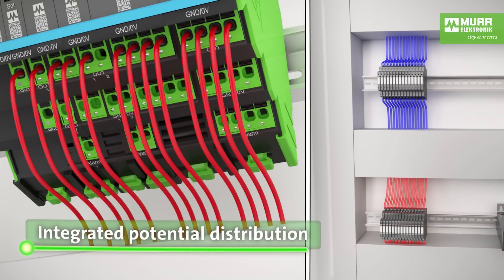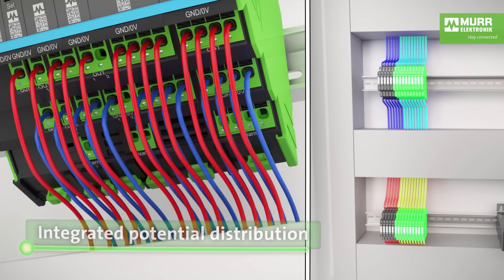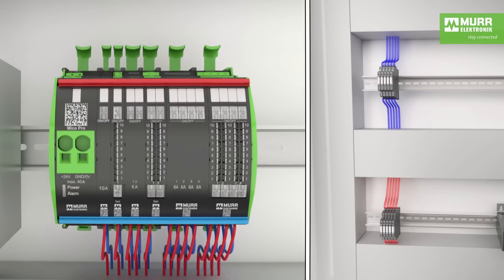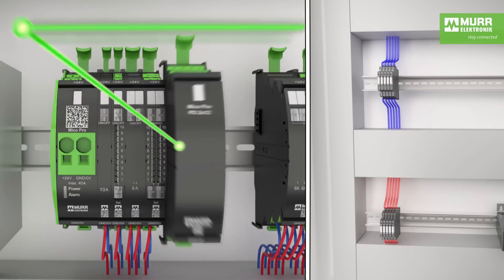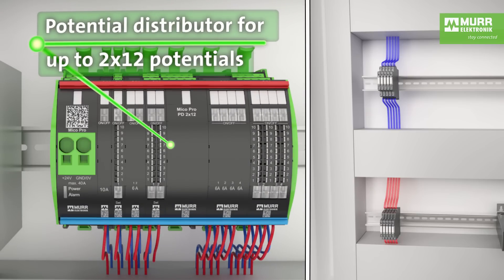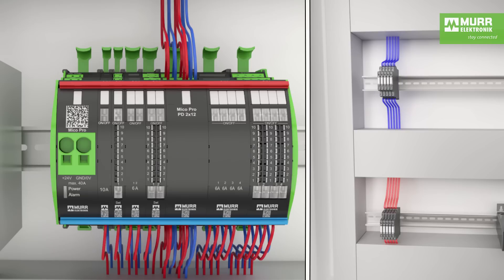Each channel has a zero volt terminal in addition to the plus terminal, removing the need for a separate zero volt terminal level in the switch cabinet. A potential distribution module allows easy termination of potential groups — for example, sensors and actuators remain grouped near the protected channel. This allows a channel to be duplicated as often as desired, providing further space savings.